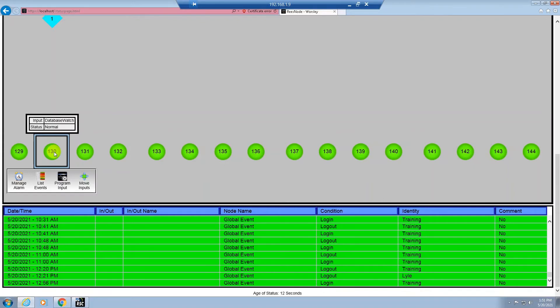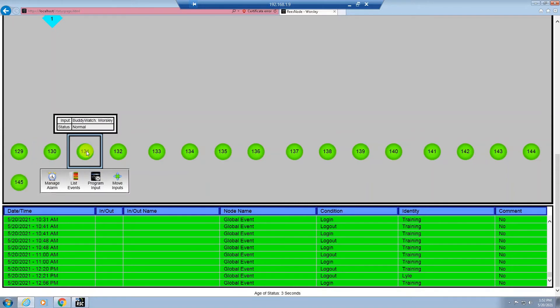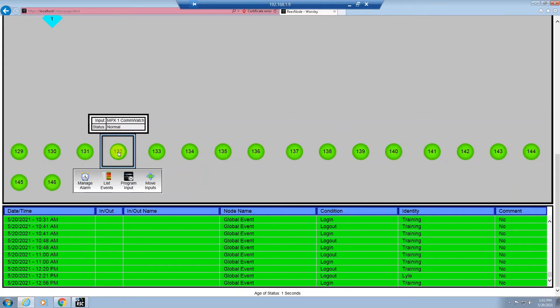You may also have to call REIS technical support for assistance. Input 131 is a buddy watch. If you have more than one node on your system, you will have this icon on your system to monitor the communications for each one of your nodes. Input 132 and all even numbered inputs monitor the communication of the REIS inputs. If your input loses communication, this input will turn brown and notify you of an alarm for this communication issue. You should call REIS technical support to troubleshoot this, and again if it cannot be fixed over the phone, a service ticket will be established to dispatch a REIS technician.